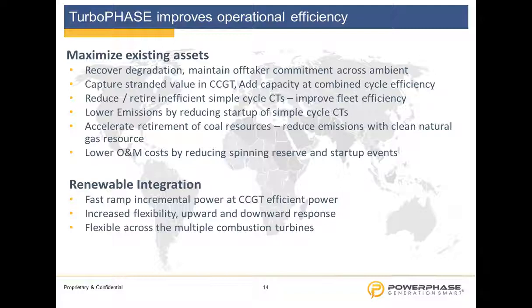And all this helps with lowering the cost of generation, lowering O&M costs, startup costs, maintenance costs, et cetera. And so when you start talking about a large fleet across a grid instead of just a particular power station, this becomes game-changing. This becomes, when we start talking about 1% in a combined cycle efficiency is huge, which is one of the OEMs recently stated. Well, 20% across the fleet is an order of magnitude change. And that all goes into allowing renewables. We all agree that renewables are good, renewables are needed in the power industry, and as they bring into the grid, it's the fact that the combined cycle gas turbines now have to start acting in a more flexible manner. And Turbophase makes that gas turbine have a much larger range of fast response and increasing that flexibility both up and down to be able to support that renewable penetration.